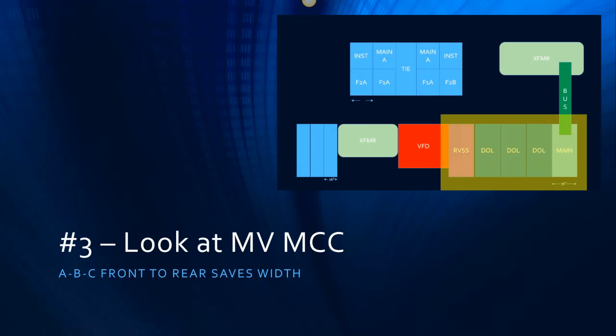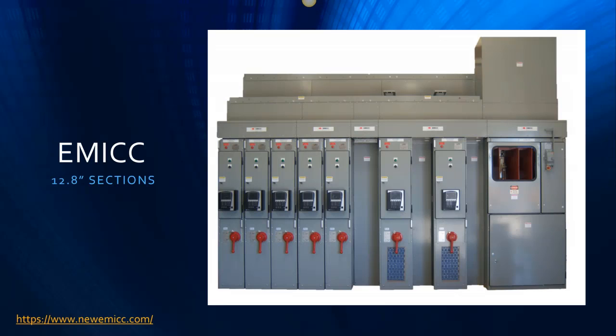Okay, so hopefully we've opened your eyes to a couple ways to get creative with the medium voltage switchgear. Let's move on to the medium voltage motor control. Traditional medium voltage motor control is almost always 36 inches wide, one high. There are occasions, I'm told, where you can do a medium voltage contactor two high, up to a certain amount of amps and horsepower, but 36 inches, that's the standard.